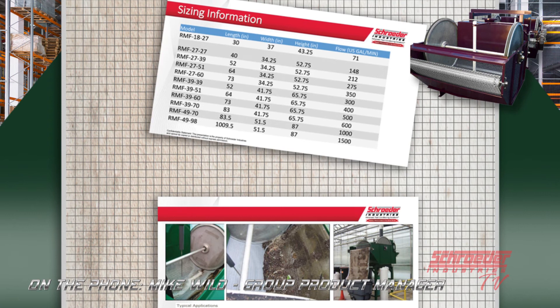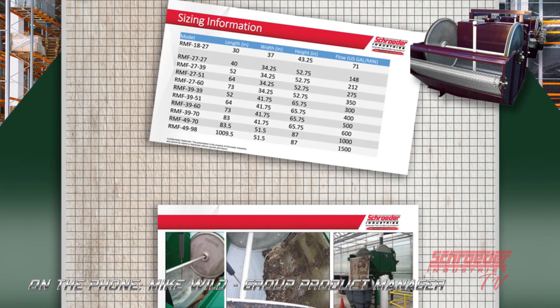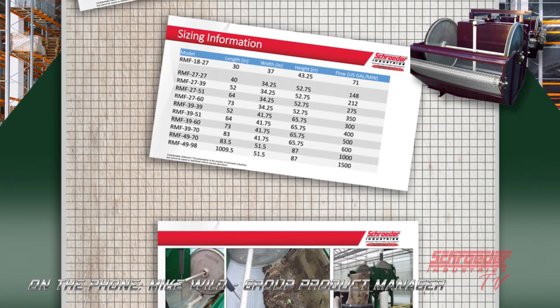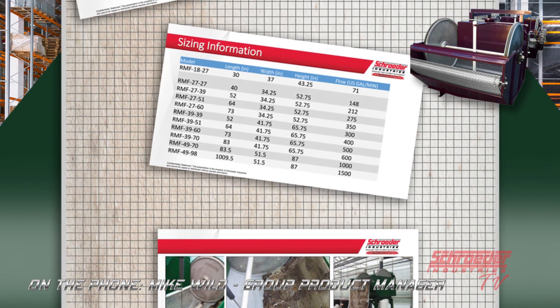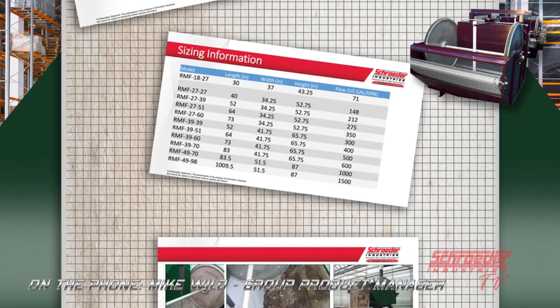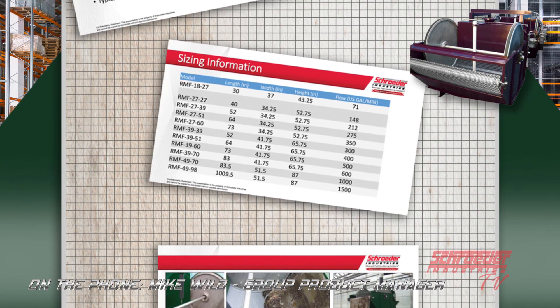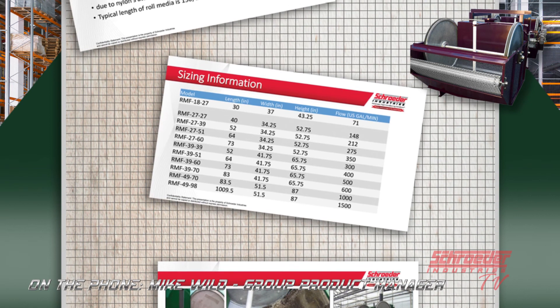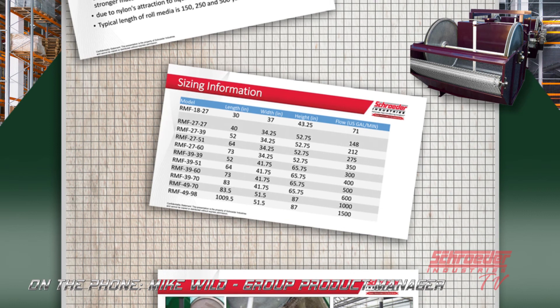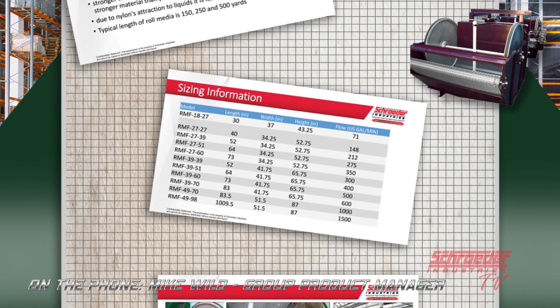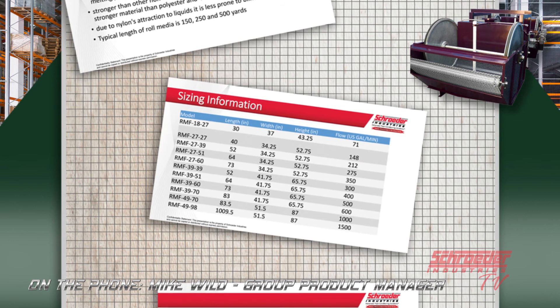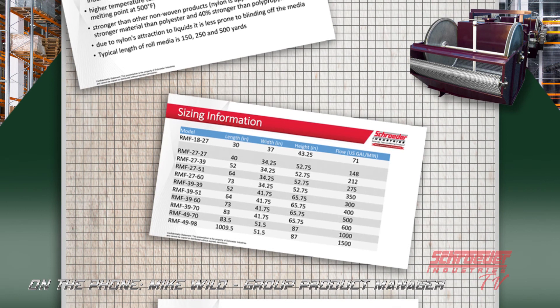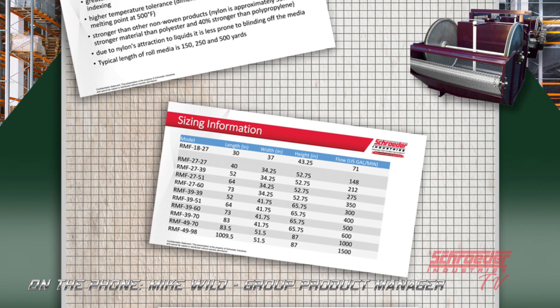When sizing the system, one of the things we like to do if we can't run a pilot is at least get samples. Flow ranges from as low as 71 gallons per minute up to 1,500 gallons per minute for the largest unit. These are just rules of thumb — real sizing takes place based on testing and the samples received. It depends on the dirt loading, the flow, and the type of fluid passing through. For heavier dirt loading, we may go to half the listed flow size, but it's very dependent on what we get back from sampling and pilot testing.